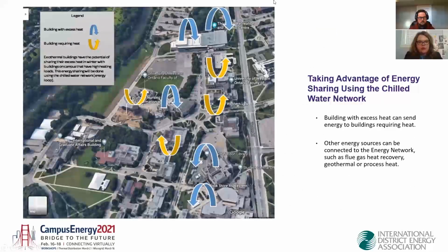So here we have the campus, and what's interesting is to see how energy can be shared between buildings. So for example, here we have the recreation center, which is usually an exothermic building, so heat has to be removed from that building. So we send it in the chilled water network. And here, for example, we have a science building that uses heat. So the heat pumps in these buildings can recover heat from the rec center and use it to heat their systems. Same thing here, we have the nursing facility, and we have other laboratories here on the network. And here, other buildings that are exothermic, for example, the student center building and the library. So all that energy sharing is possible because of that energy network, or the chilled water network, connecting the buildings.